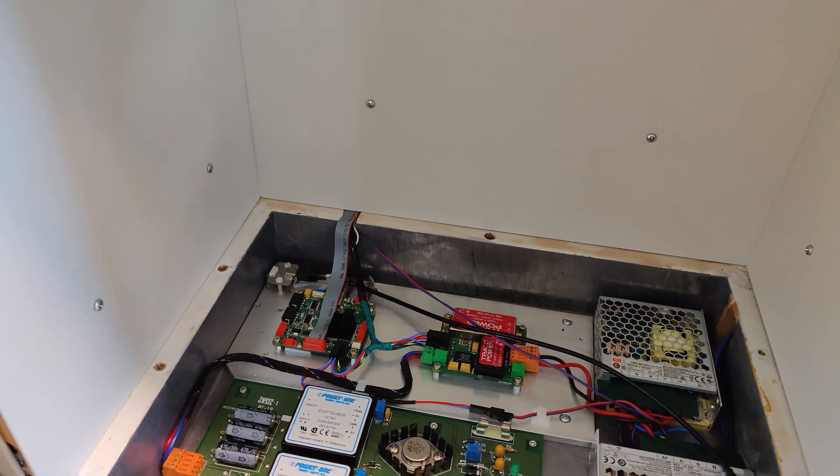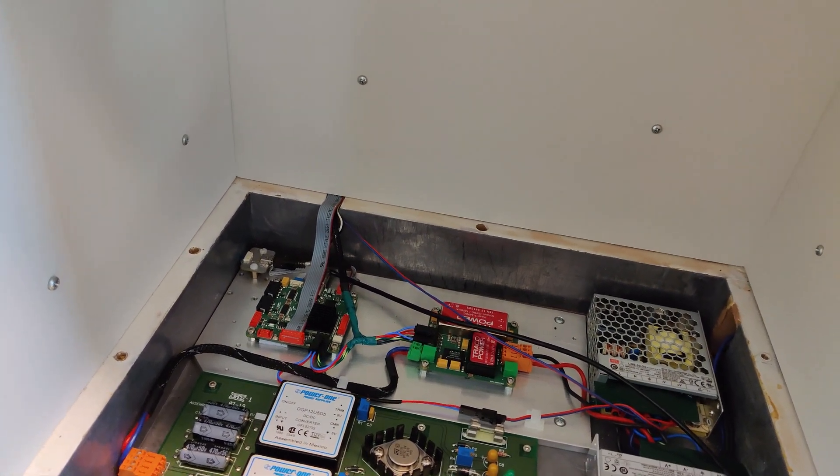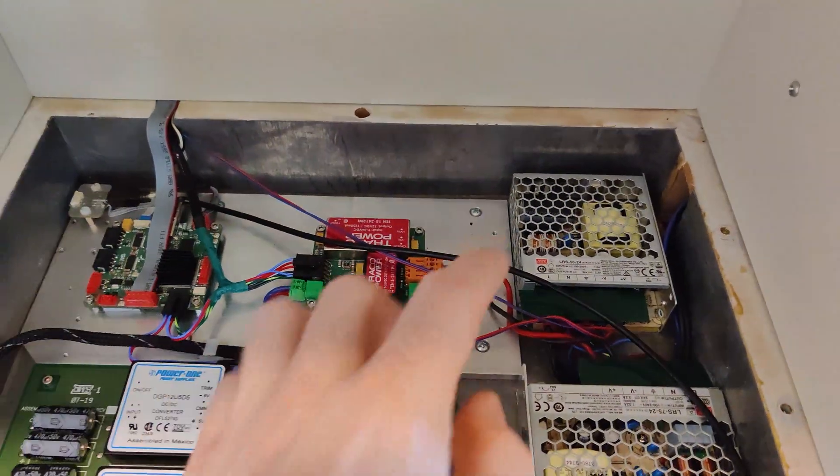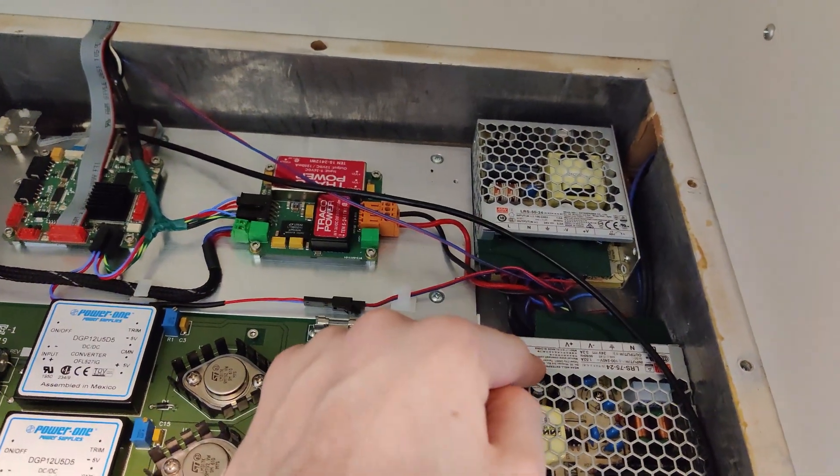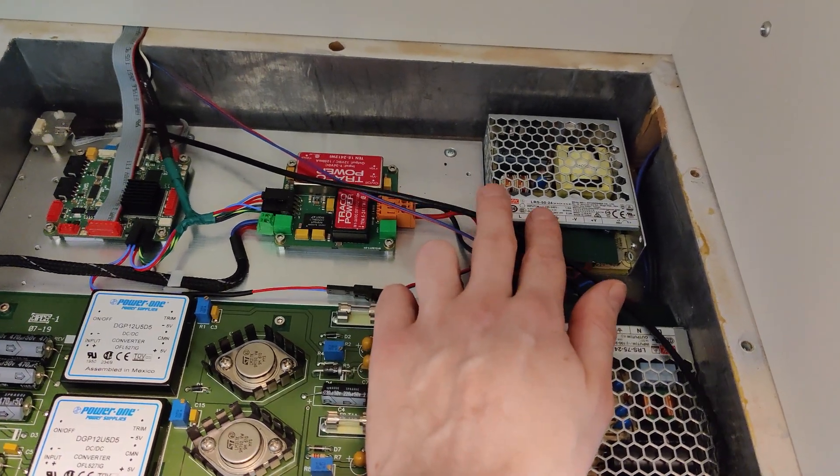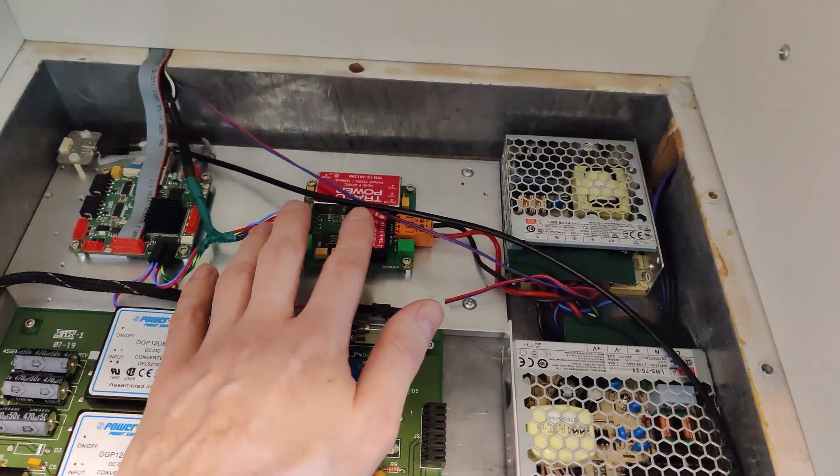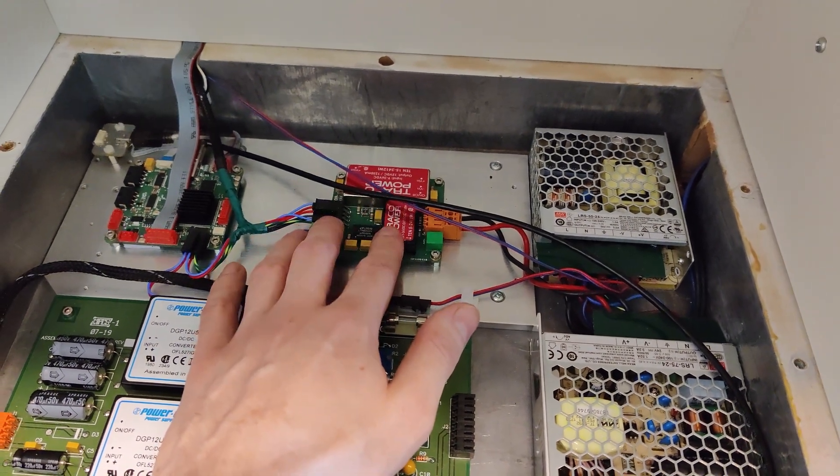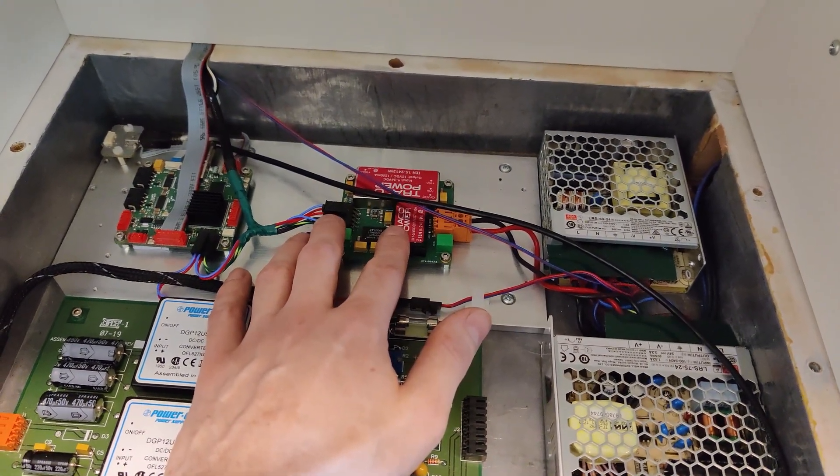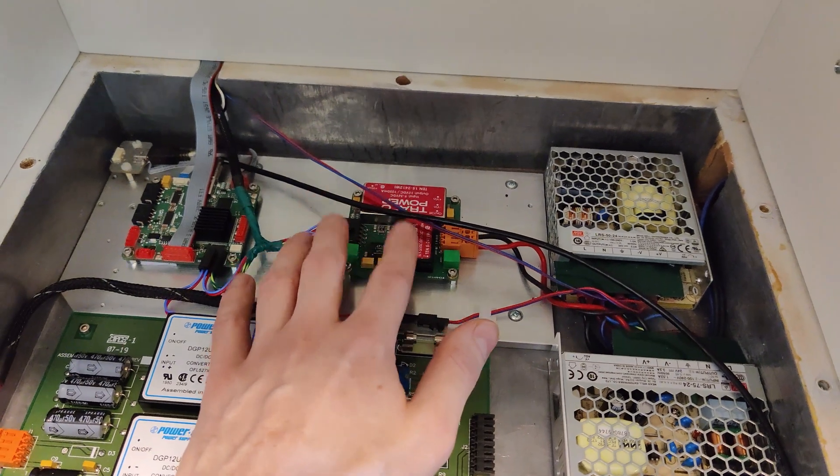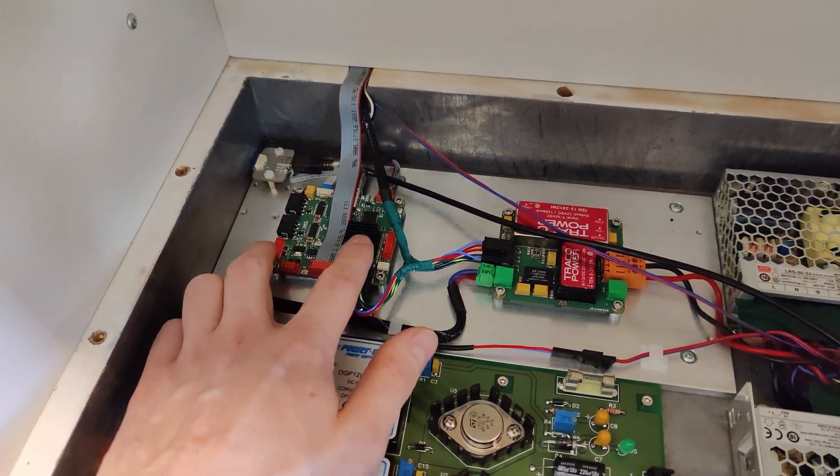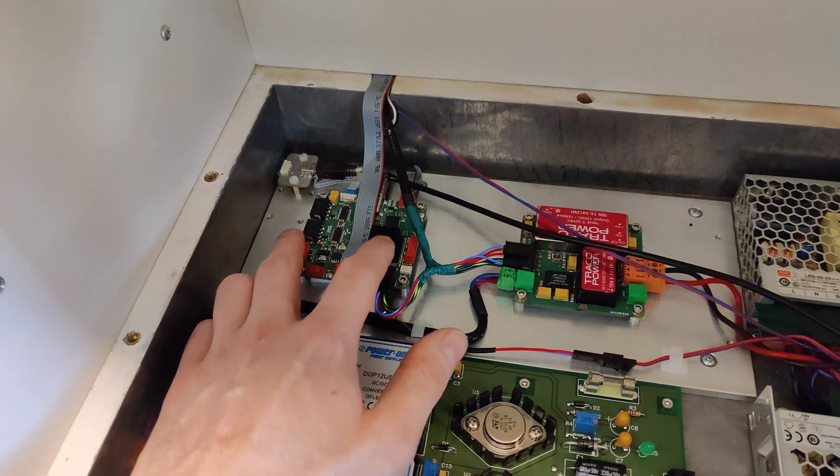We have the output of the tube - this is a micro focus tube. Here we have power supplies: one for the tablet, one for the x-ray controller. We have a step down to 5 volts, 24 volts, 12 volts, and minus 12 volts for the x-ray control, the x-ray generator. Here we have the FPGA and x-ray controller for timing and motors.